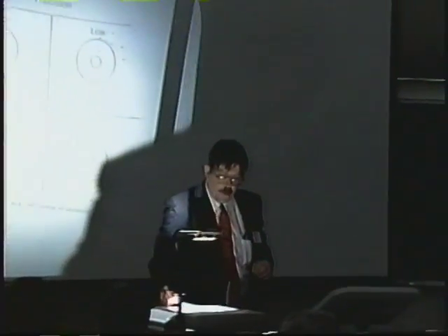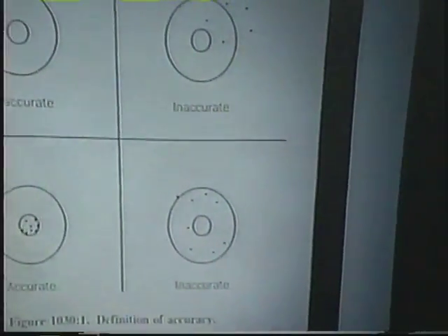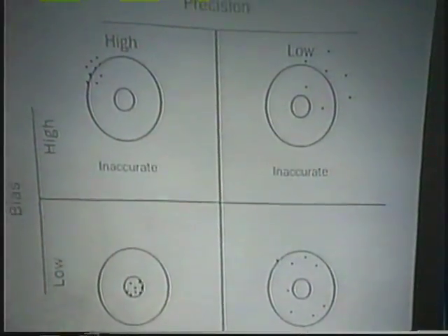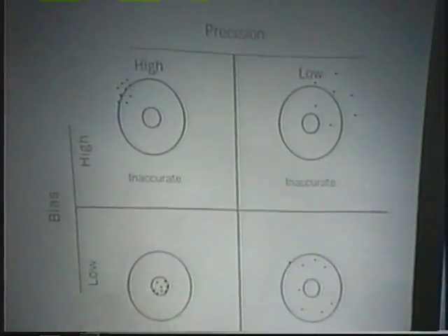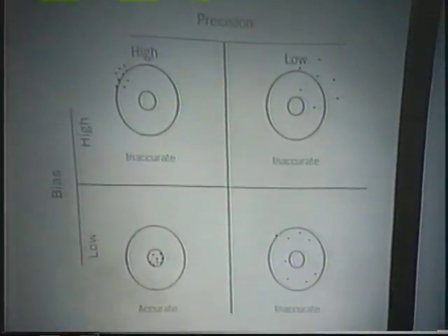And that's where quality control comes in. We obtain samples from other companies that are assayed and certified to have a particular concentration. And we analyze those solutions, and if they are not within a particular set of limits, then we know that our work is not particularly accurate.